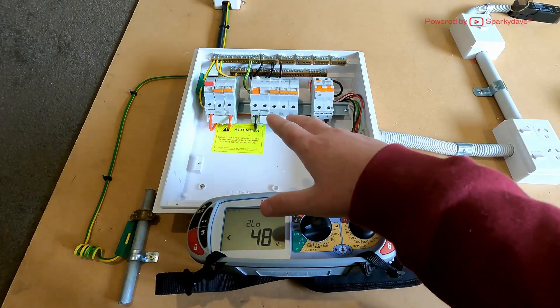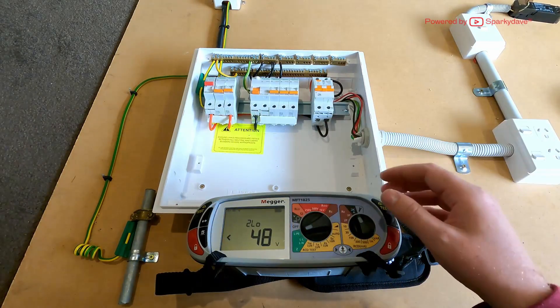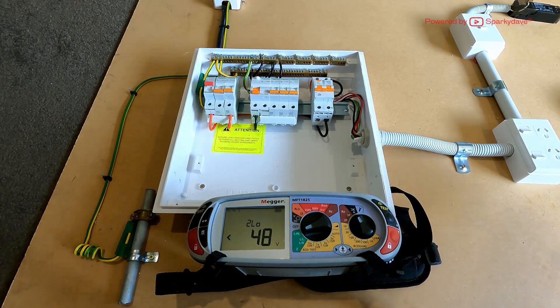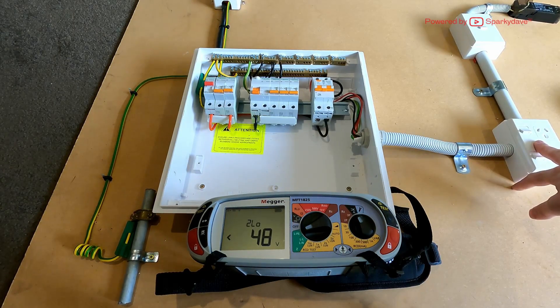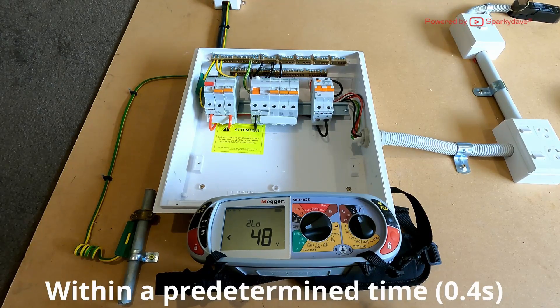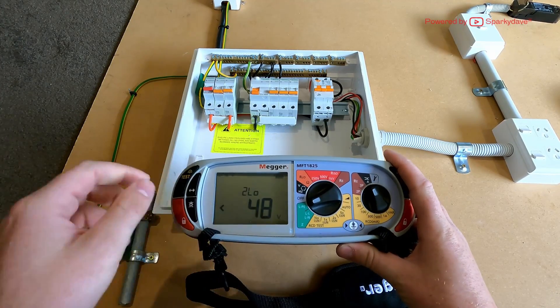When we're doing these tests, we want to do one at the switchboard to ensure that the circuit protection is going to work under fault conditions. Then we do our second test at the furthest socket from the installation to ensure that the longest path has an impedance low enough to operate the circuit protection under fault conditions.